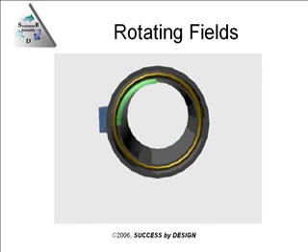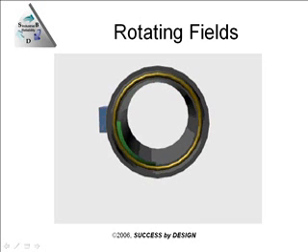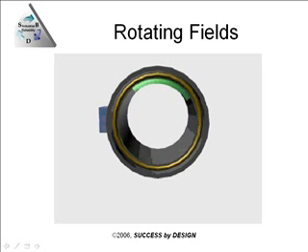There are a number of animations in this presentation. This first one shows a green bar rotating inside the image of a stator. This is supposed to represent rotating fields generated by bringing in three-phase voltage to the motor, which develops a current inside the windings — and that current is directly related to a rotating field. This rotating field rotates inside the motor at a pace of 120 times the line frequency divided by the number of poles of the machine. Poles are always in pairs because you have a north pole and a south pole. So for a 60 hertz, two-pole electric motor, that would be 120 times 60, or 7,200, divided by 2 — giving 3,600 RPM synchronous speed.